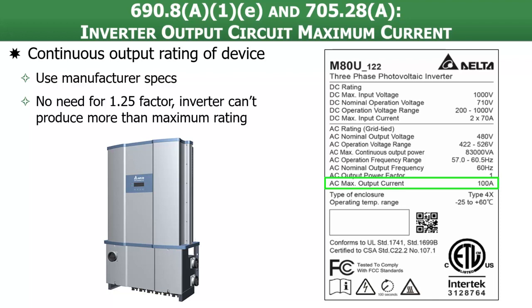And there's no need for that additional 1.25 safety factor that we had to use when we were calculating PV source and output circuit maximum current, because the inverter can't produce any more than its maximum ratings, and that's per the listing of the inverter as well as the way the inverter is designed and programmed. It's not going to exceed the output ratings that you see on the label or on the spec sheet.